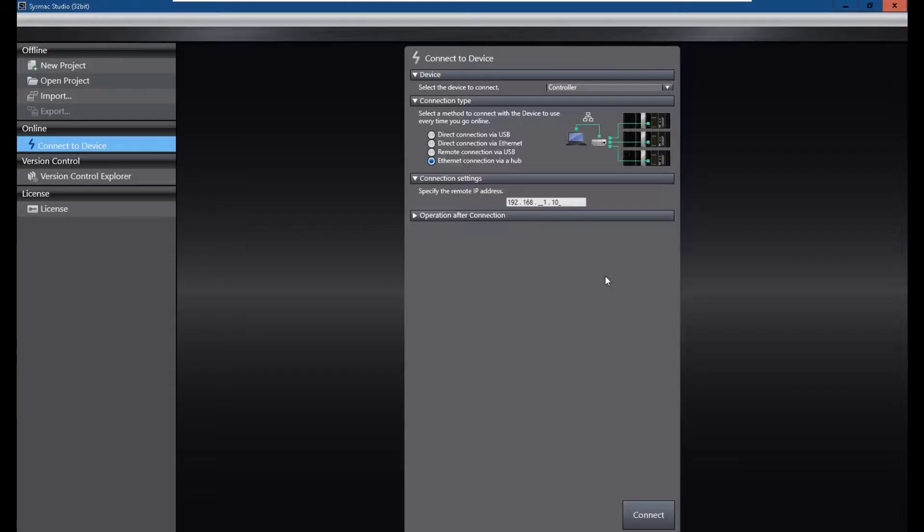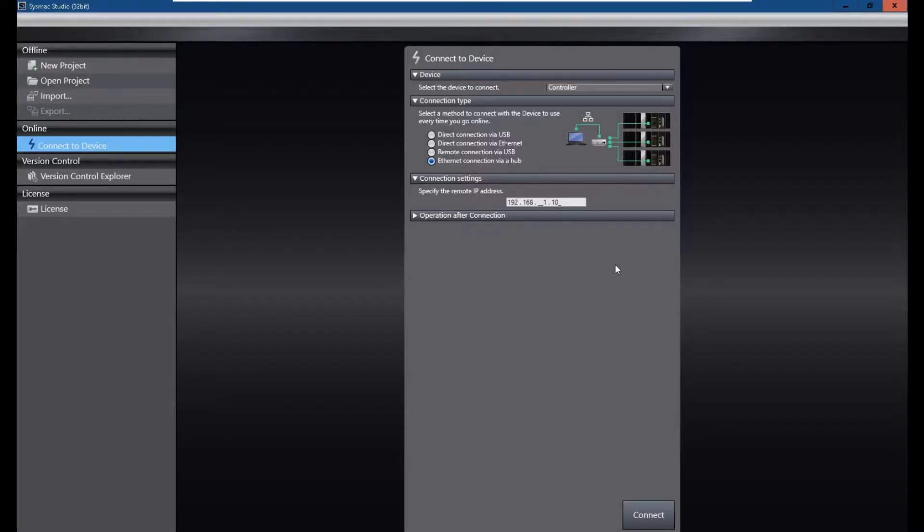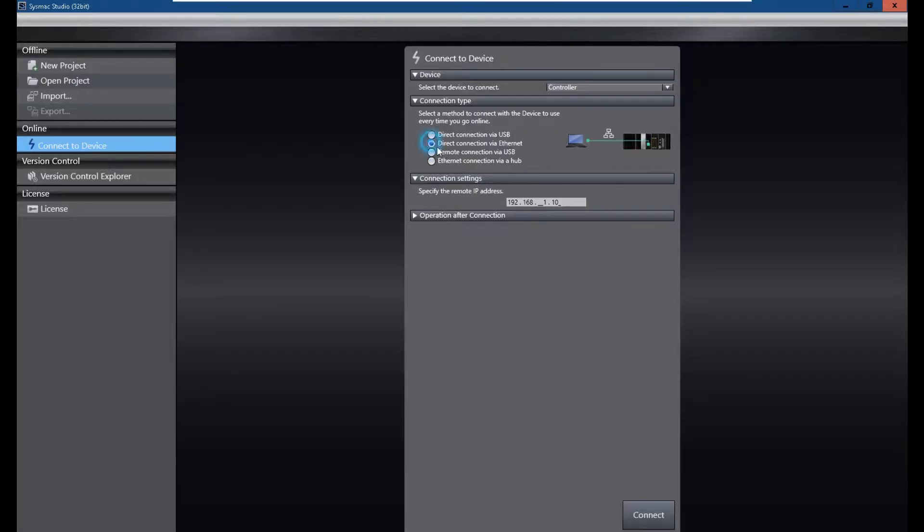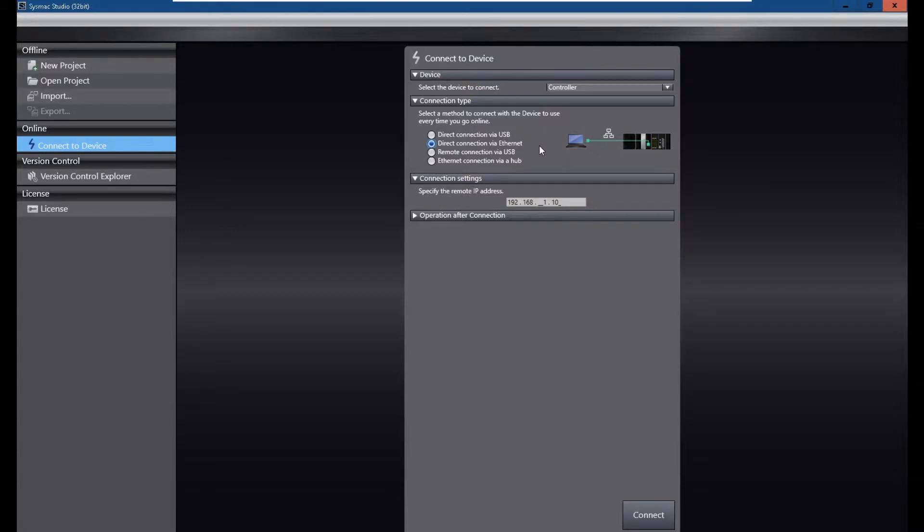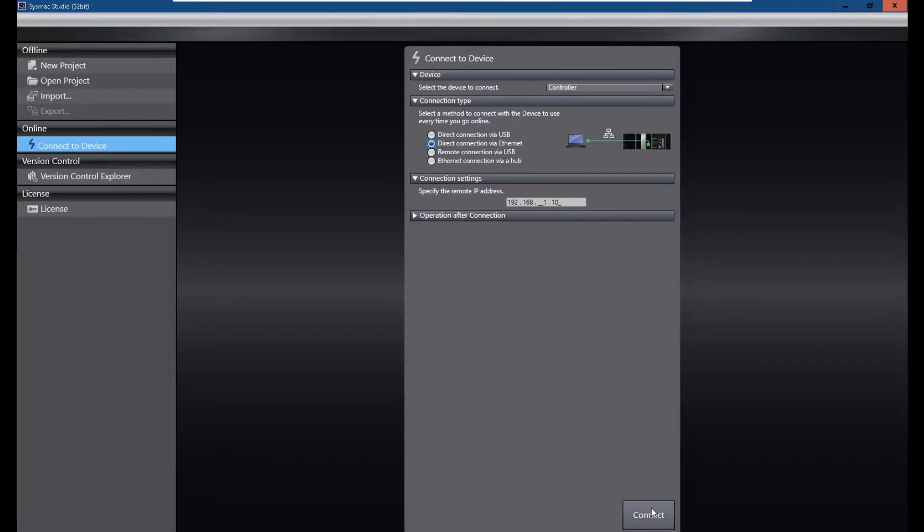But most of the time, if you are programming on site, most of the time you don't know the actual IP address or you cannot remember the IP address in this controller. So the easier way is we can select direct connection via Ethernet. Using this way, we can use one cable, use your laptop, peer-to-peer connected with this controller. After selecting this, let's directly connect with this controller and hit the connect.